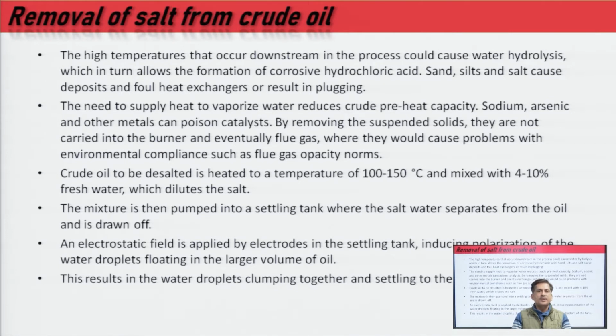The mixture is then pumped into a settling tank where the salt water separates from the oil and is drained off. Now, an electrostatic field is applied by electrodes in the settling tank, inducing polarization of the water droplets floating in the large volume of oil. This results in the water droplets clumping together and settling to the bottom of the tank.